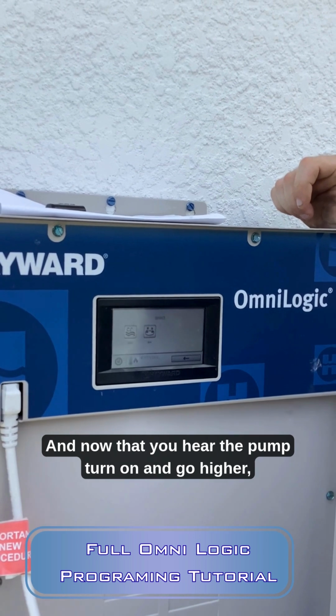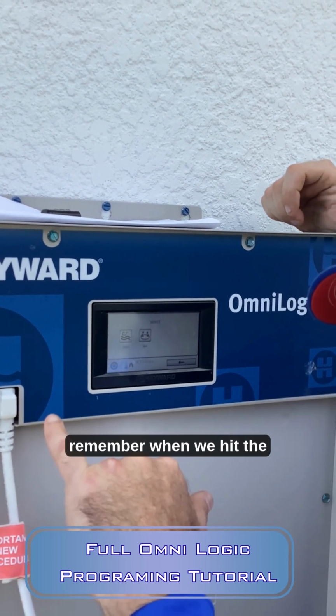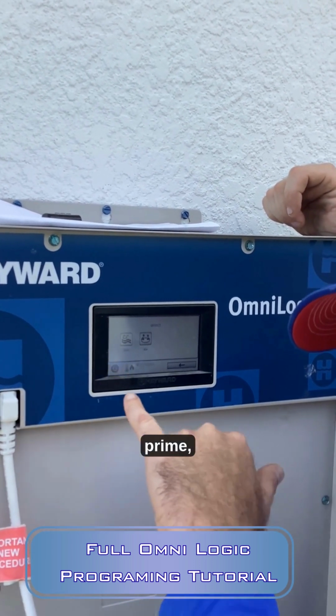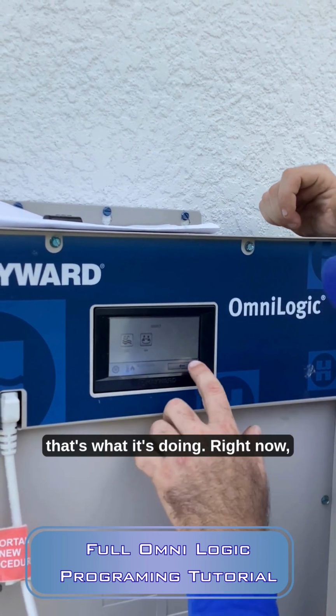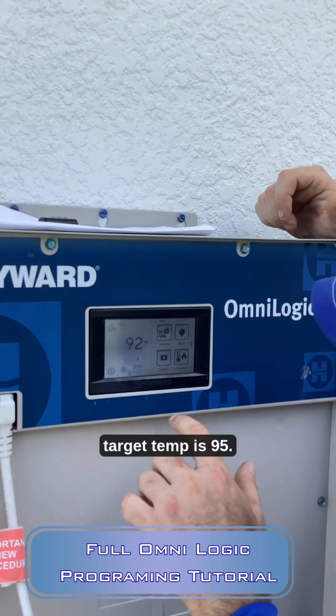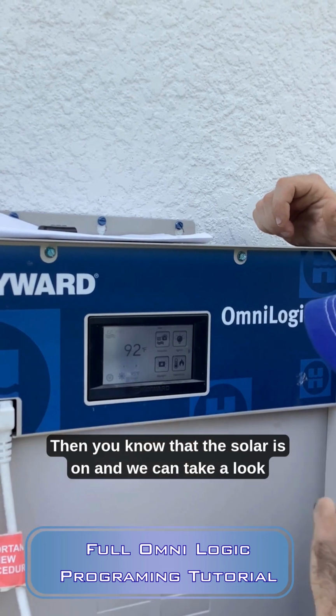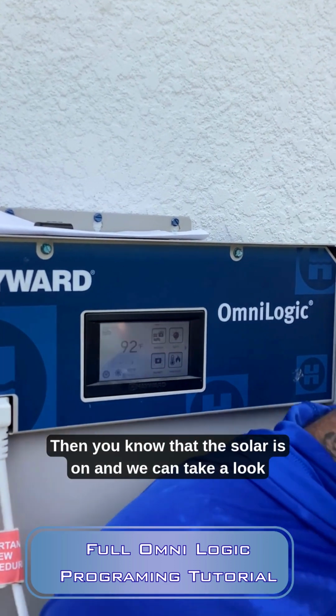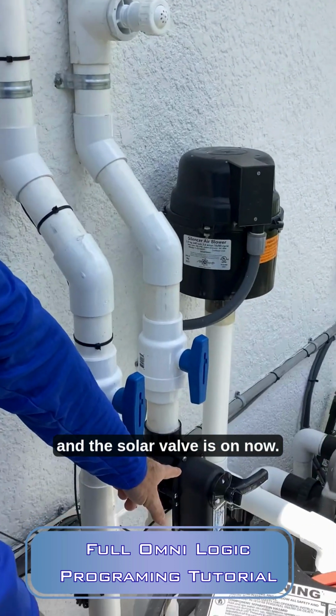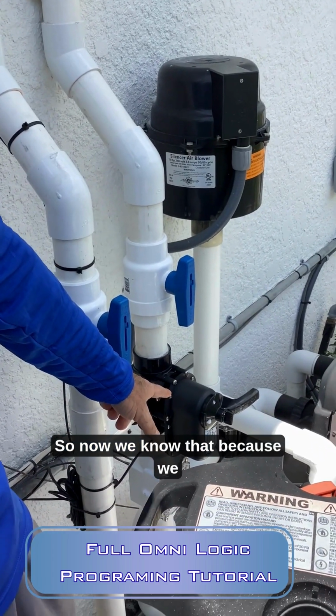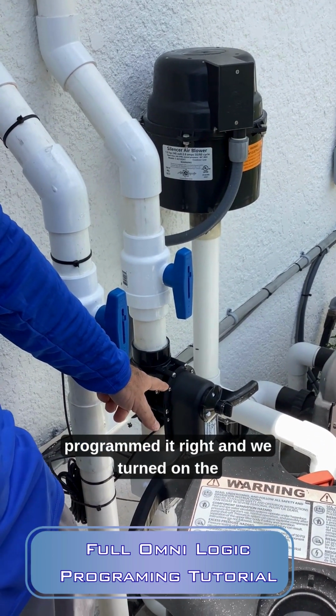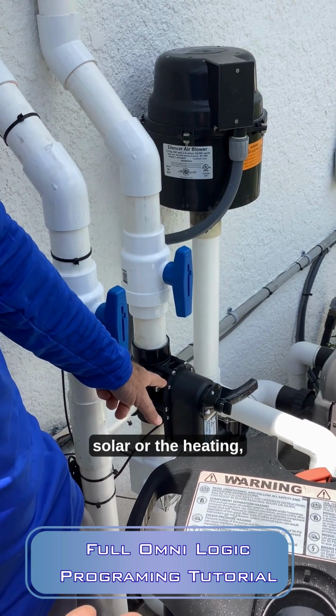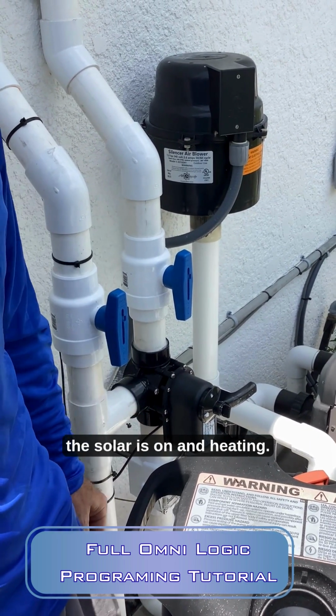And now you hear the pump turn on and go higher. Remember when we selected the prime, that's what it's doing right now. Target temp is 95, letting you know that the solar is on. And we can take a look, and the solar valve is on now. So we know that because we programmed it right and turned on the heating, the solar is on and heating.